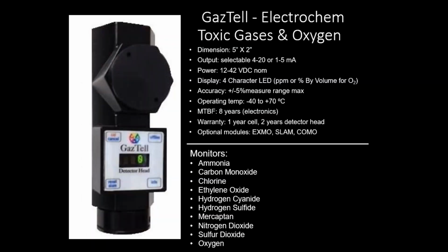GazTell electrochemical. Okay, right now, if you look on the bottom of this slide, you'll see all the gases that we're capable of doing right now using this GazTell electrochemical detector head. The difference being that the electrochemical cell, when it is replaced in the body, can see different types of chemicals. And you can see ammonia, carbon monoxide, chlorine, ethylene oxide, and so on and so on.